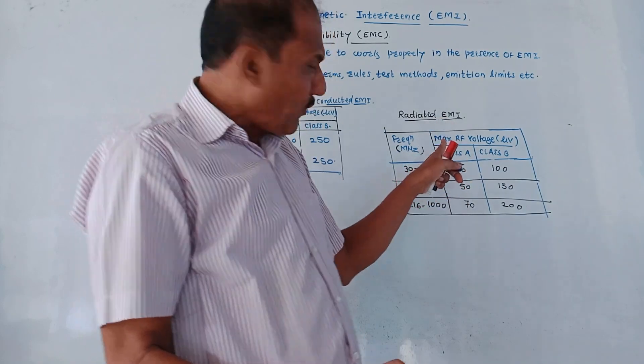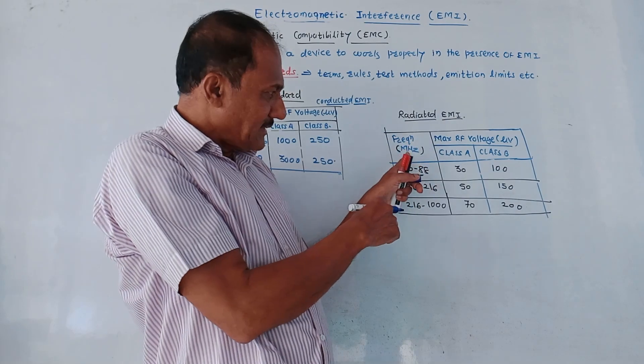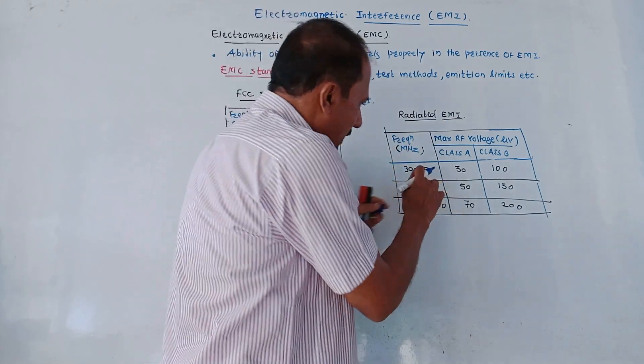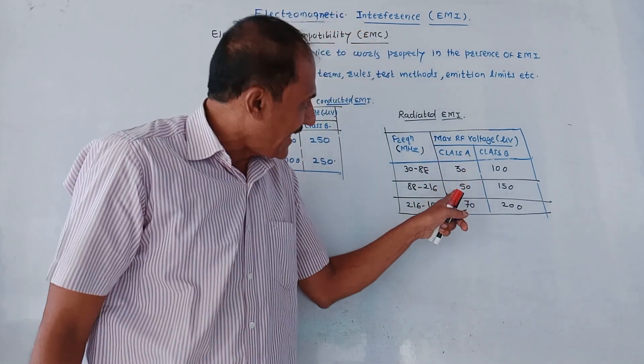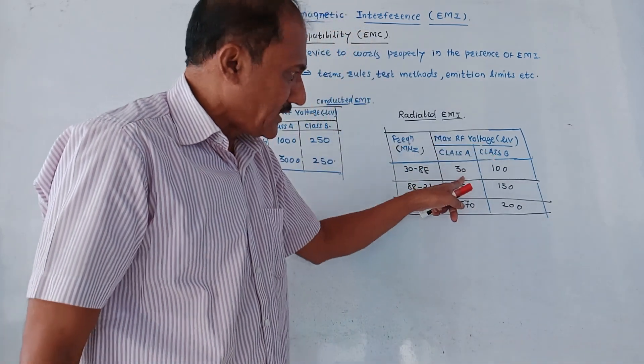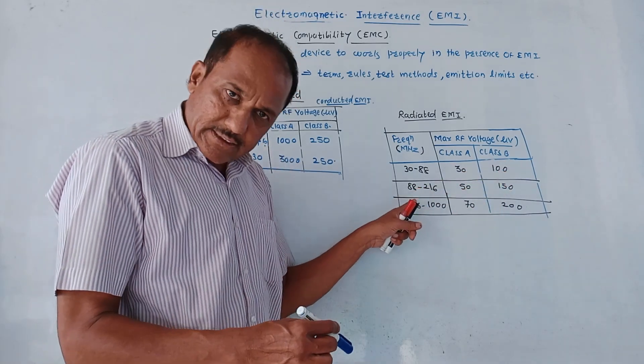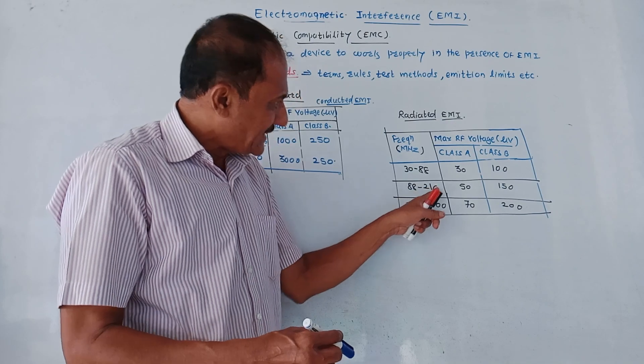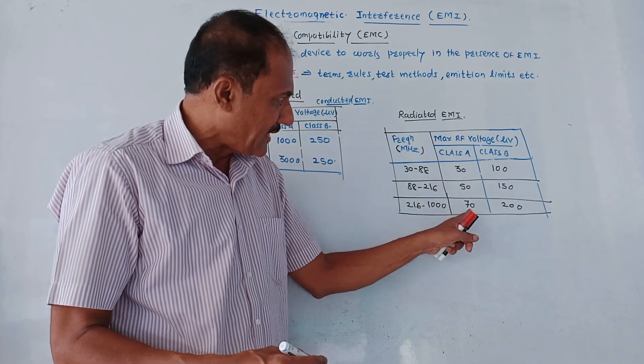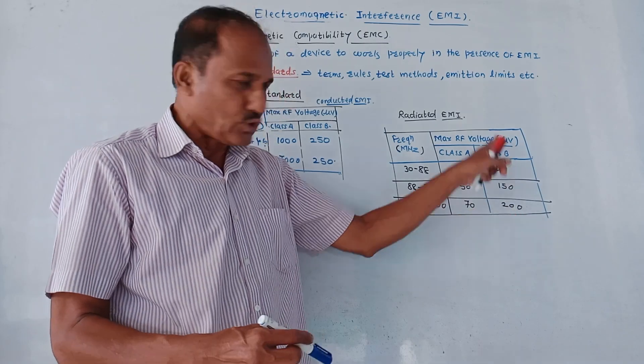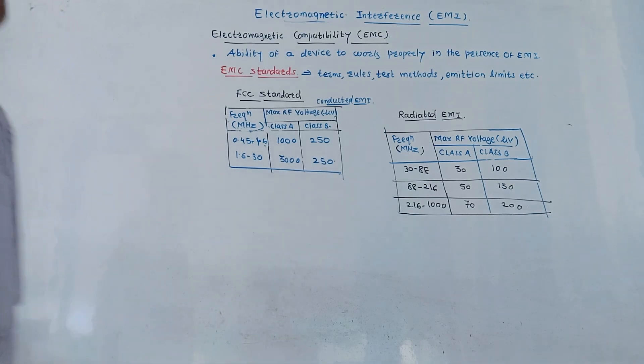For radiated EMI, again using the same parameters with frequency measured in MHz: if the range is 30 to 88 MHz, then for class A the maximum RF voltage is 30 micro-volt, and for class B it is 100 micro-volt. For the frequency range 88 to 216 MHz, the values are 50 and 150 micro-volt respectively. For 216 to 1000 MHz, class A is 70 micro-volt and class B is 200 micro-volt. This is about EMC and EMC standards.